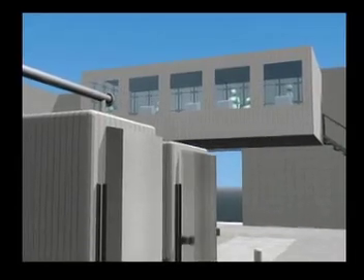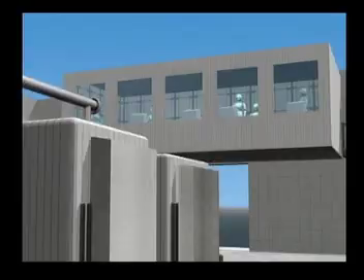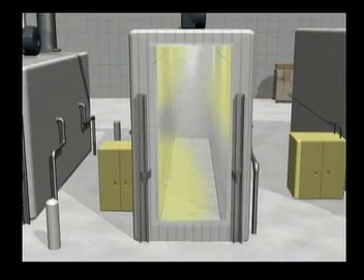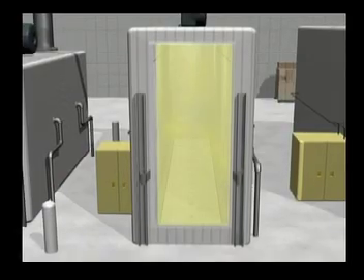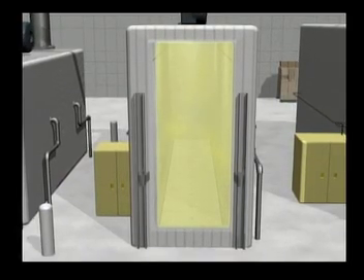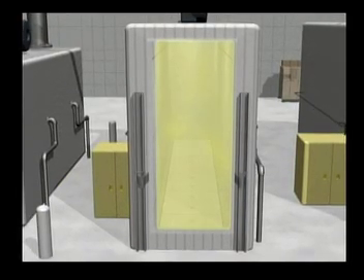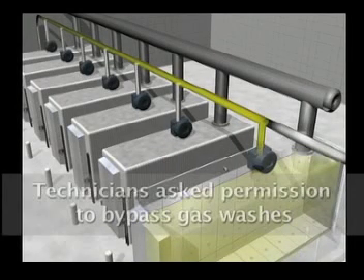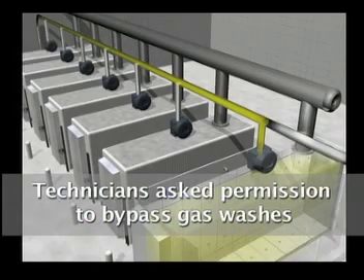Maintenance technicians arrived and performed tests, which did not reveal any problems. They then ran a test cycle that injected 120 pounds of ethylene oxide into the empty chamber, and again they could not identify a problem. As the system performed the first step of pumping ethylene oxide to the scrubber, the technicians asked the supervisor for permission to bypass the time-consuming gas washes. The supervisor agreed.